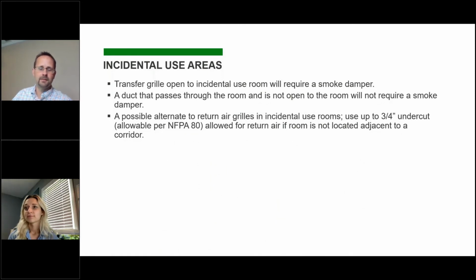Yeah, and another thought on that table: it has changed over the last 10 years. There are a lot of designers who are still implementing, just out of habit, criteria that was in an older code that's no longer required. So for some mechanical rooms or even some storage rooms, where people are used to rating every single storage room, that's not necessarily required anymore. So again, look at the code that you're designing under and don't just use old habits and create ratings where we really don't need ratings and where we don't really need dampers. Again, these rooms may not be rated, but in a healthcare occupancy, your soil storage and clean utility will be 1 hour rated based on this incidental use space.